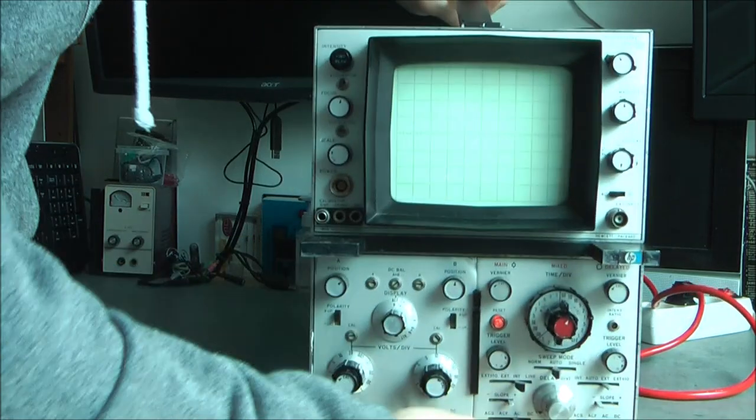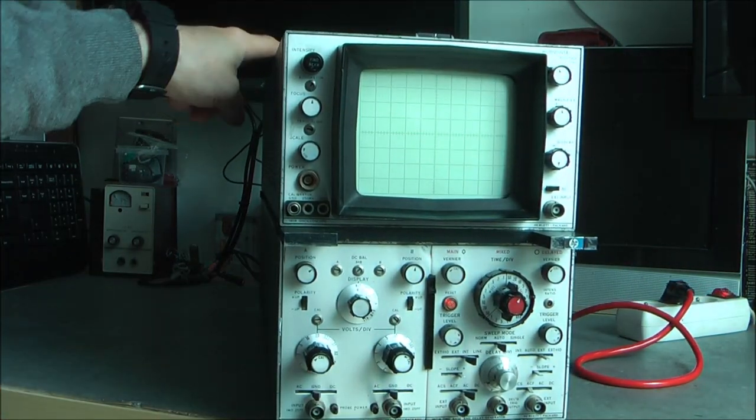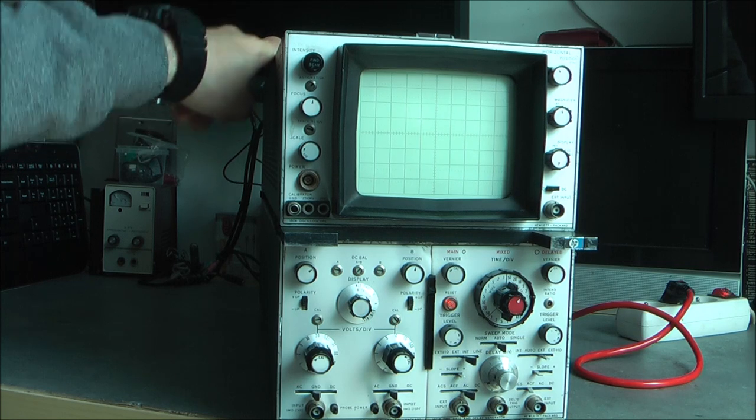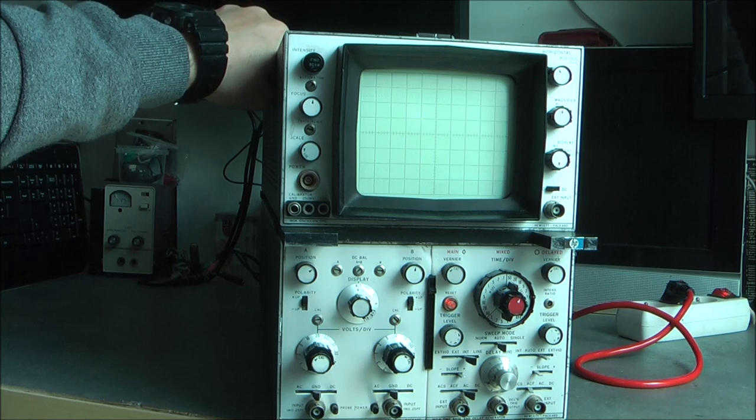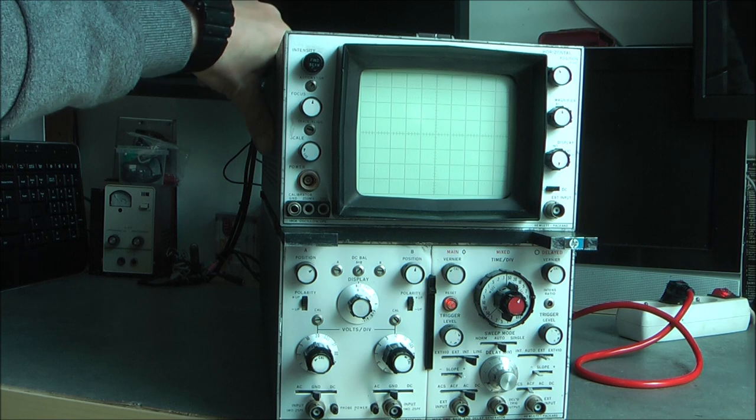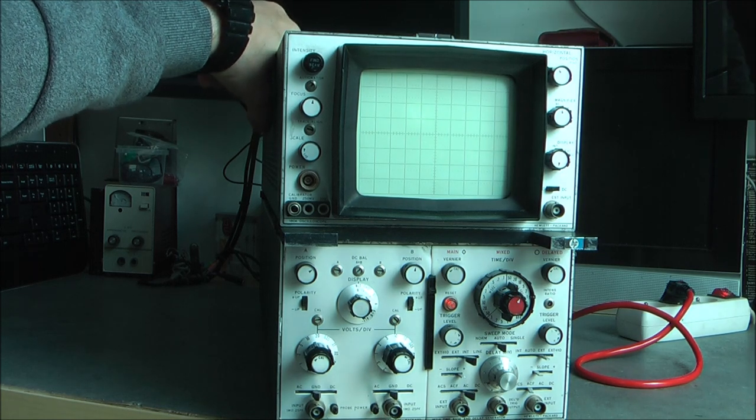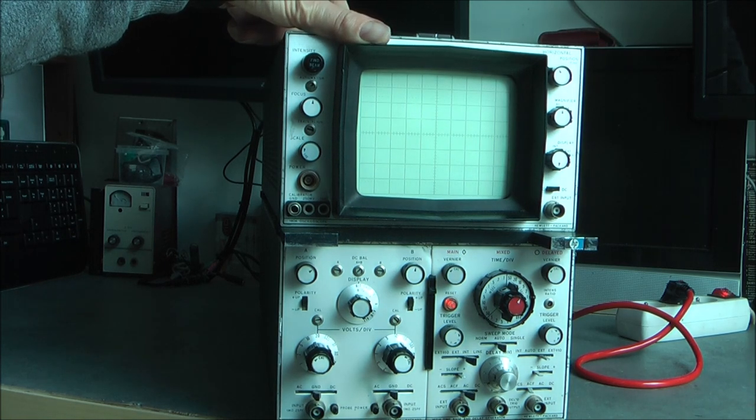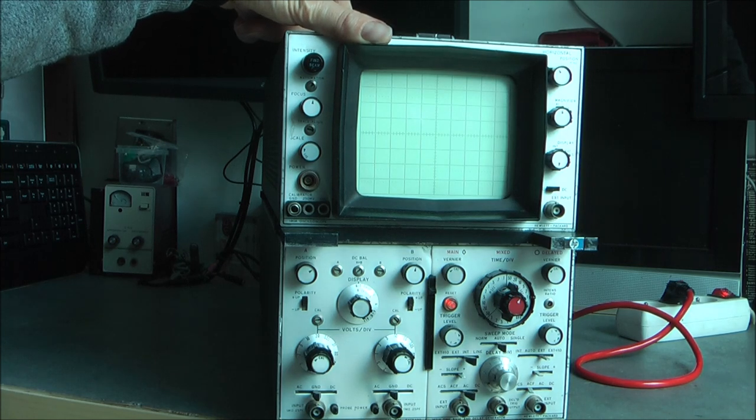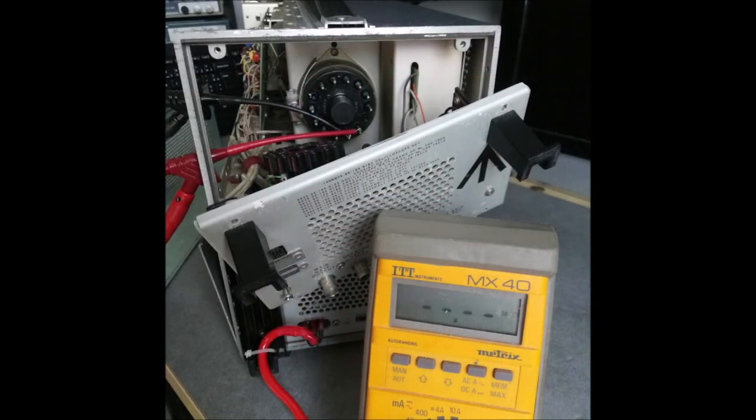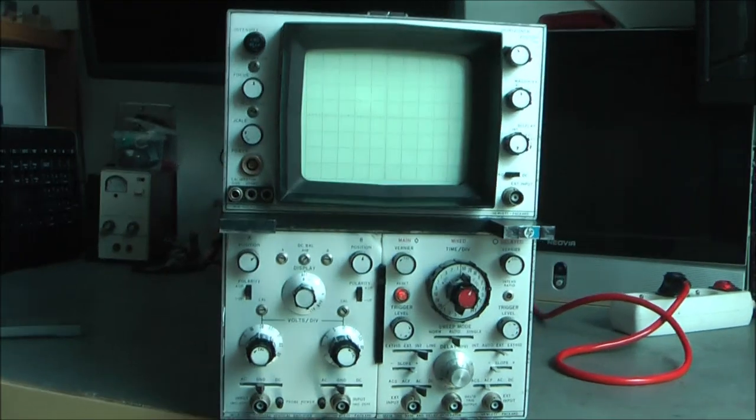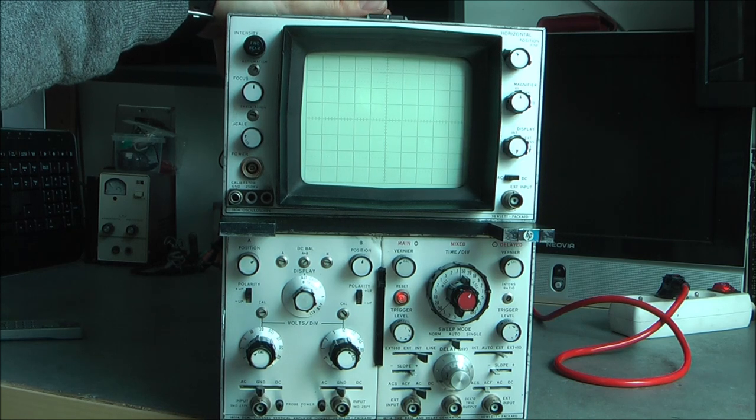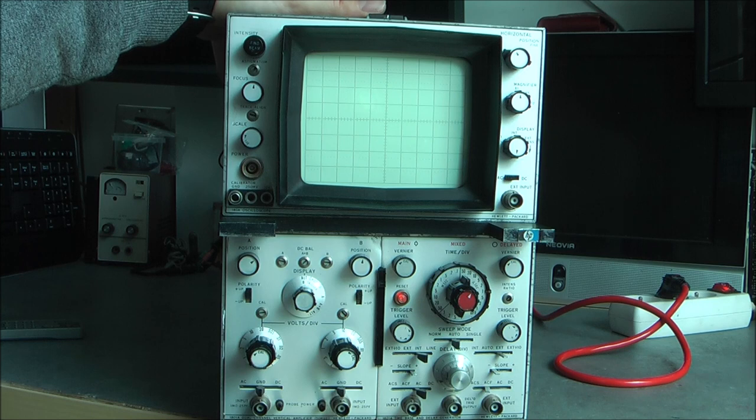You find the maintenance manual on the web, not a very good scan but it is free and it allows to diagnose. When I did find no beam, I did first check the power supplies, they are good. I did check the oscillator transistor in the primary side of high voltage transformer, it is good and it is oscillating. What I did do also is check the CRT filament and yes, it is the problem. Naturally the CRT filament is cut open.